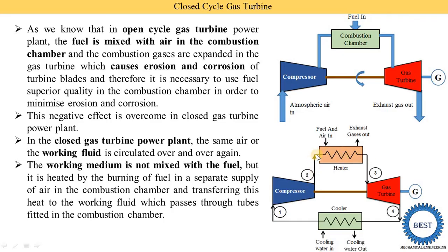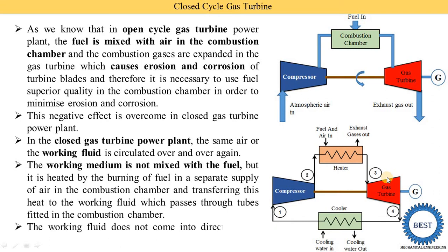The compressed air or other gas is passed through the tubes, and the combustion of fuel is carried out outside the tubes. So it is one type of heat exchanger — an indirect type. The air passing through the tubes absorbs heat energy from the combustion product. The working fluids and the combustion product are not mixed. The working fluid is continuously recirculated through these four components, so erosion and corrosion chances of the gas turbine blades are reduced. The working fluid does not come into direct contact with the product of combustion because the working fluid is inside the tubes and the combustion product is outside.